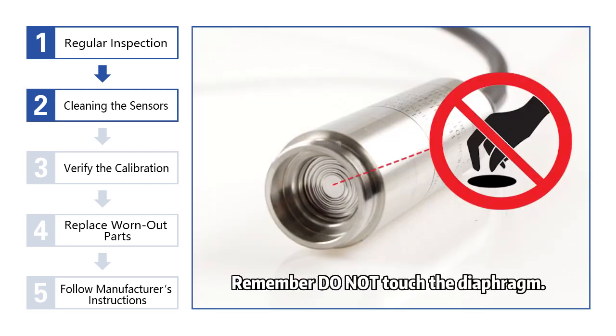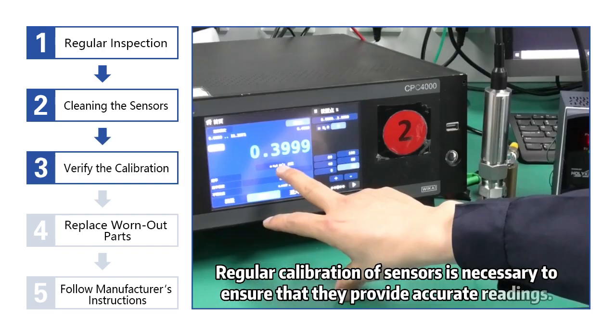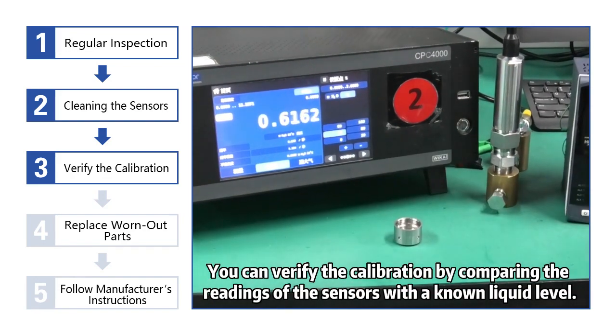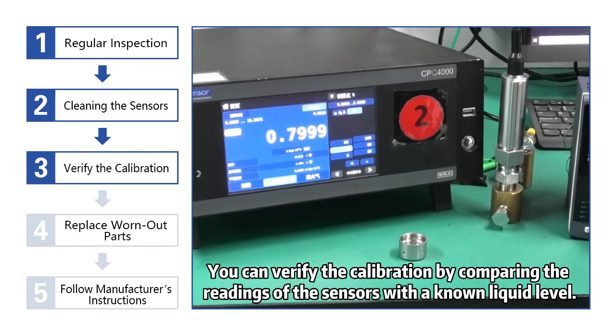Remember, do not touch the diaphragm. 3. Verify the calibration. Regular calibration of sensors is necessary to ensure that they provide accurate readings. You can verify the calibration by comparing the readings of the sensors with a known liquid level.